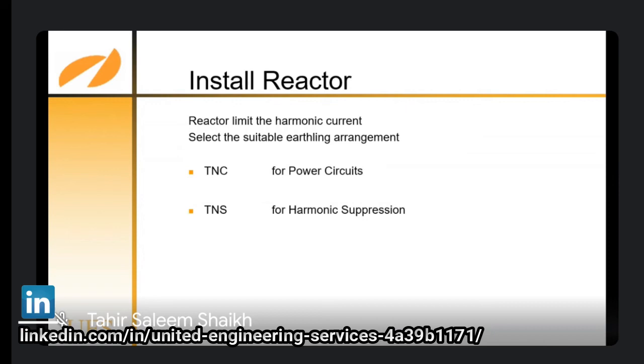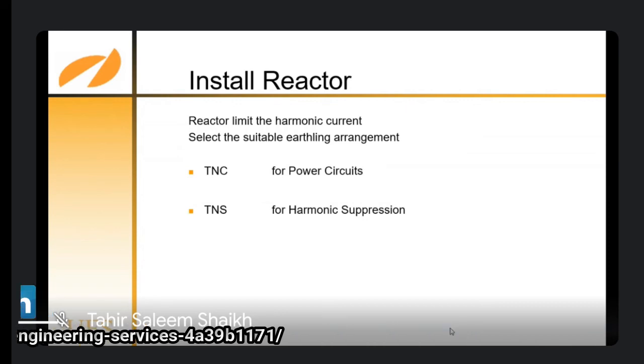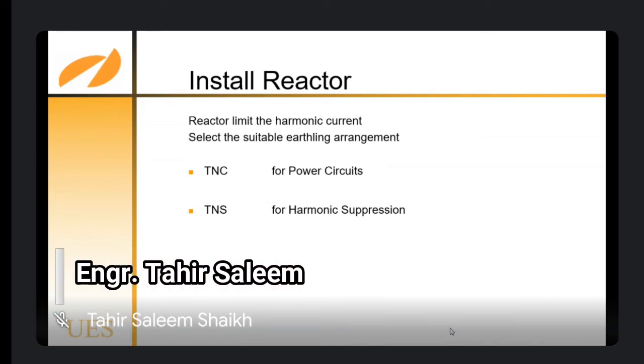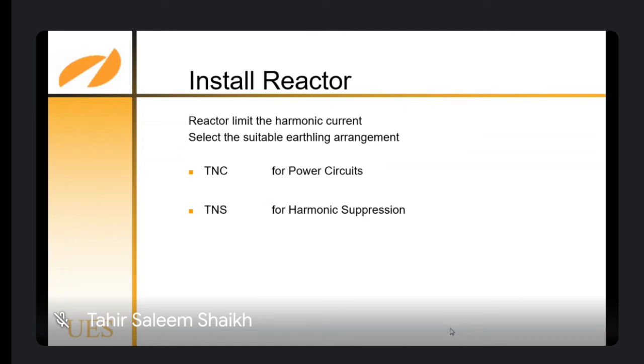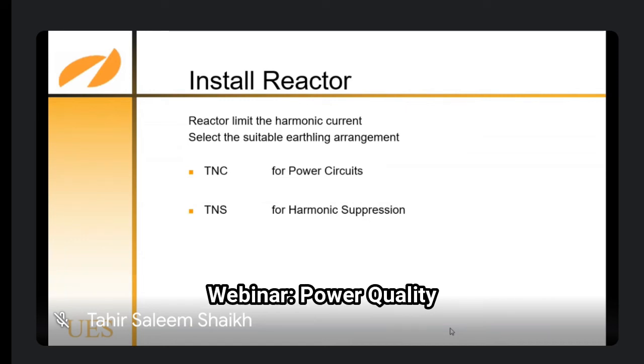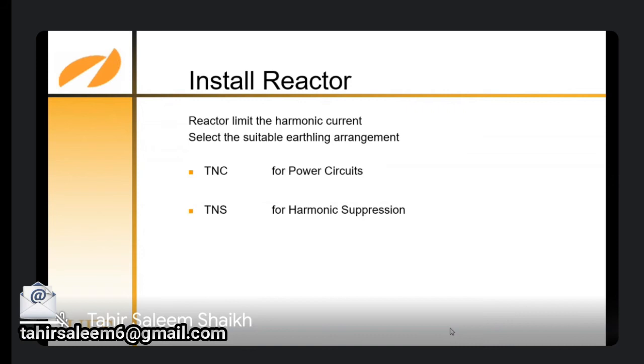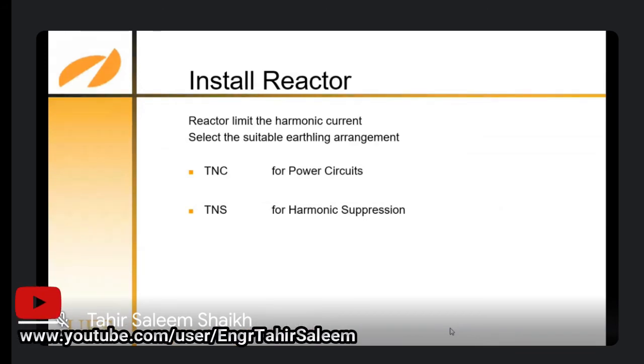Series reactors are reactors that limit the harmonic current. I will show you what type of filter over here. But there is also very important information: the earthing system should be TN-S. What do you mean by TN-C? TN-C is the earthing system where the neutral and ground are the same. The same cable carries the neutral current as well as the ground currents. In the TN-S system, the neutral and ground are common at the power source.